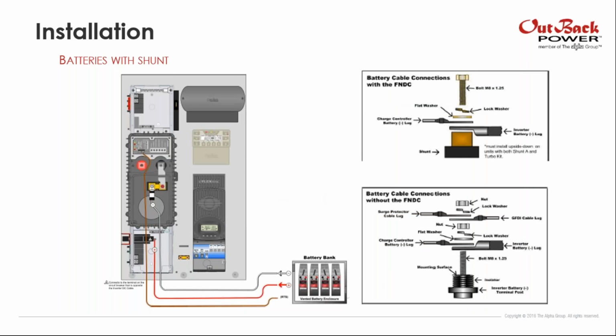The next part is the installation of the batteries with the shunt. Here we have two different types of cable connections. The first one is when you have the FlexNet DC. You will need to put the bolt, a lock washer, a flat washer, then the charge controller battery lug and the inverter battery lug. Everything will be put on the shunt. If you do not have the FlexNet DC, you will have to put it in the terminal post of the inverter. That's the difference.